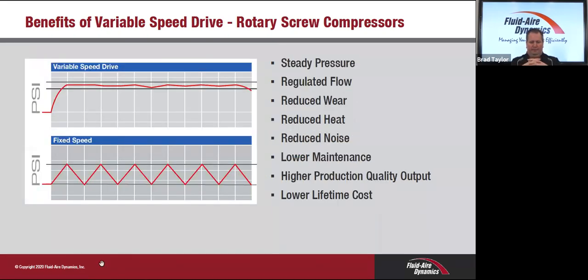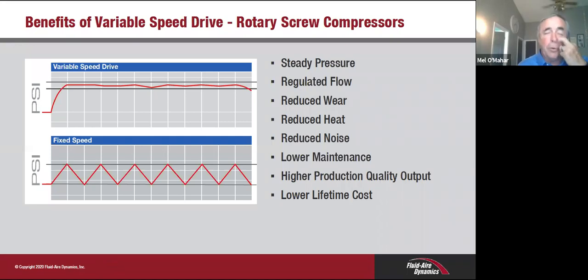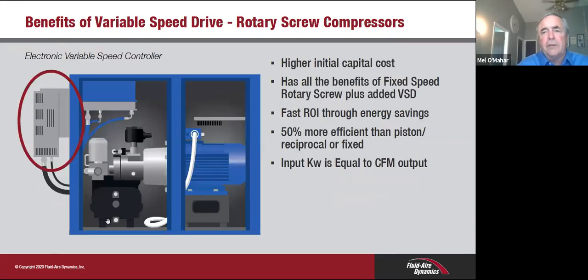Next slide there. Say, Brad, if I could just add a couple of points to that, that are on there. With the variable speed compressor, in most cases, customers are looking at energy savings as definitely the biggest benefit. But with slower speeds, you have less noise, you have more durability with some of the components and things like that.